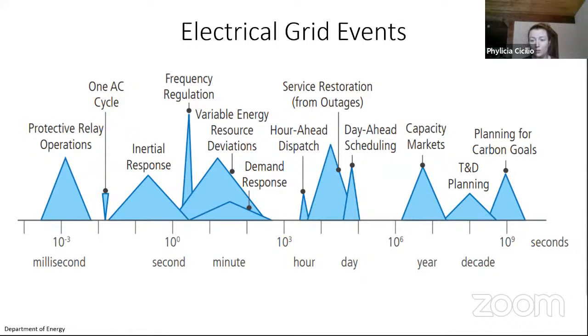Then moving left, we start to get into events. They're getting to what I call dynamics. Demand response is a control that signals specific loads to turn on or off as a regulation mechanism. Then there is frequency regulation, which is also enacted by power sharing controllers, usually directly connected to the generators. Then there is inertial response, which was discussed earlier about inertia, and then protective relay operations. Now, protective relays are what are used to disconnect devices to either protect themselves or prevent cascading outages.